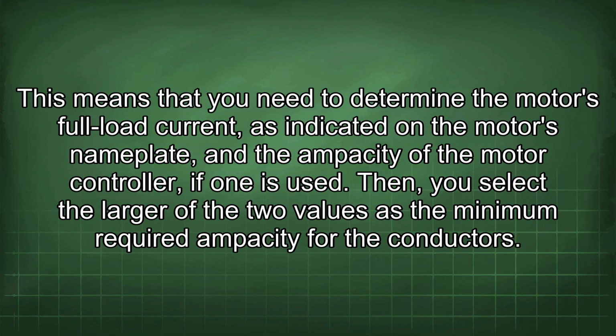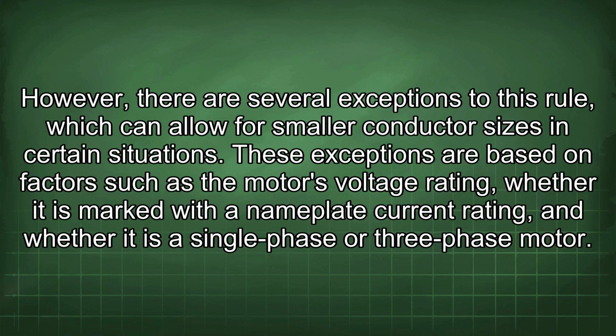This means that you need to determine the motor's full load current, as indicated in the motor's nameplate, and the ampacity of the motor controller, if one is used. Then, you select the larger of the two values as the minimum required ampacity for the conductors. However, there are several exceptions to this rule, which can allow for smaller conductor sizes in certain situations.